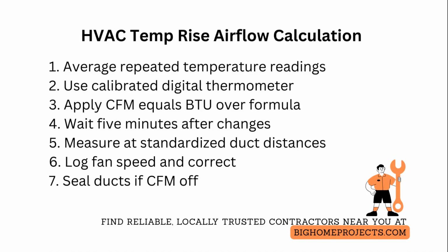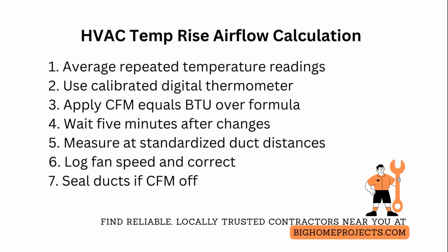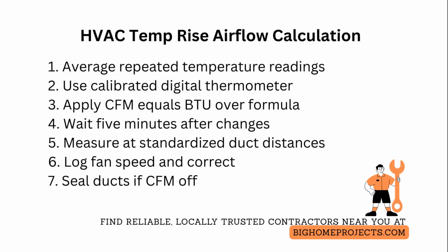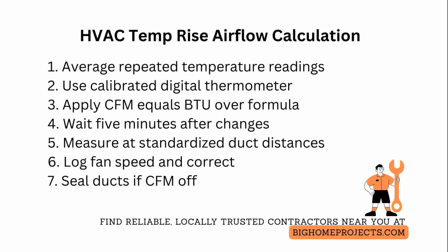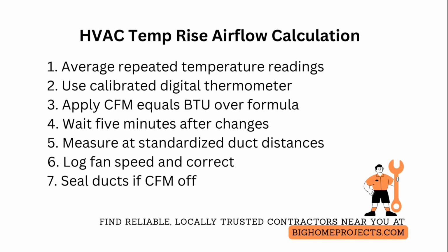small but meaningful errors. Always document instrument serial numbers, locations, and ambient conditions, so future retests can be compared. Use the same thermometers and mounting technique to minimize systematic bias. Finally, whenever measured CFM differs from design by more than 10%, trace duct leakage with a blower door or duct blaster test to quantify loss rather than relying solely on temperature rise results.